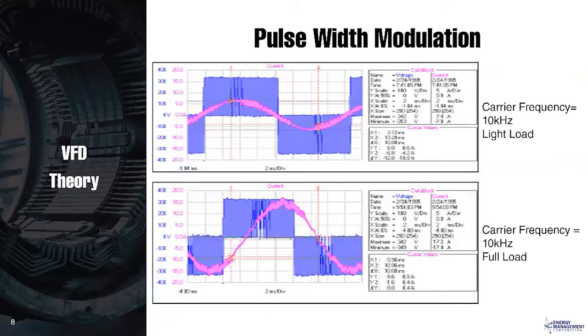It's a PWM waveform, and that's why you need a very accurate RMS meter in order to measure that, because most meters will not really measure that voltage waveform very accurately. And if you want to get even close to accurate, you really need a high-speed true RMS meter. Fortunately, we can see the voltage on the keypad of the drive, and that is very accurate. Next slide.